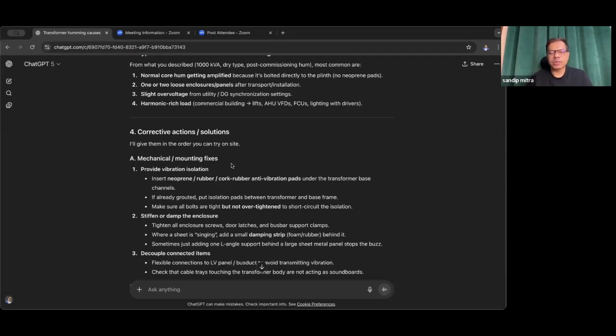Provide vibration isolation. So as earlier also it has been explained, insert neoprene or rubber or cork rubber anti-vibration pads under the transformer base channels. As per your project, different specifications may be mentioned. Just check there. If already grouted, put isolation pads between transformer and the base frame. Make sure all bolts are tight but not over tightened, so as not to short circuit the isolation.